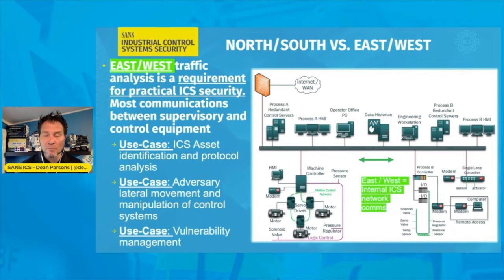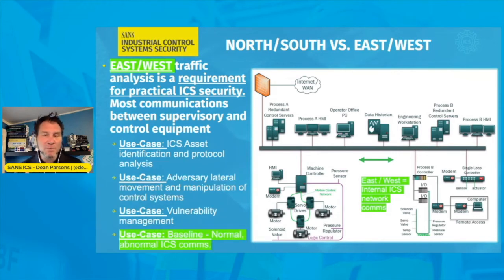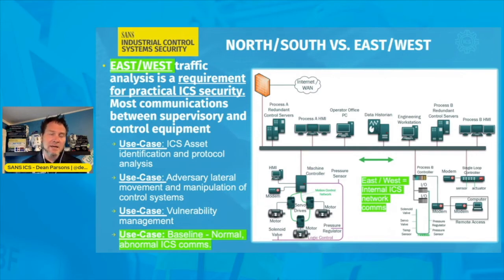Beyond lateral movement detection, there is vulnerability management. Collecting data passively in this area can reveal what types of software are running at this location, as well as the hardware devices, which aligns with ingesting threat intelligence and understanding what vulnerabilities may exist. Last but not least, the most beneficial aspect of east-west traffic collection is being able to baseline the ICS network. Understanding what normal operations look like is key, and it helps you identify outlying events and anomalous activities at this level.